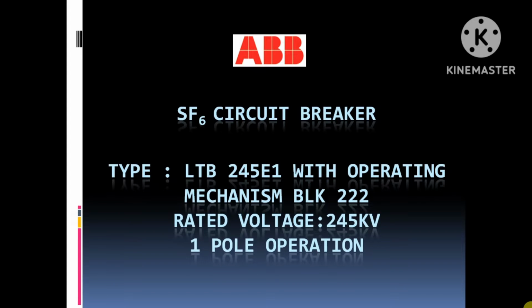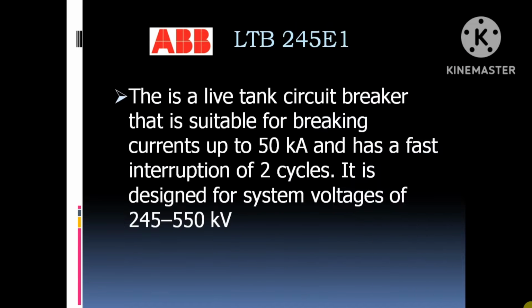Its rated voltage is 245 kV and it's single pole operation. LTB means live tank breakers. It's suitable for breaking currents up to 50 kiloamps, and it has a very fast interruption of 2 cycles, and it is designed for system voltages from 245 to 550 kV. That means it is suitable for 220 kV and 400 kV substations.